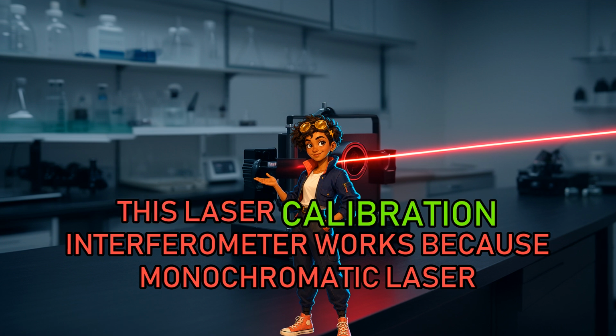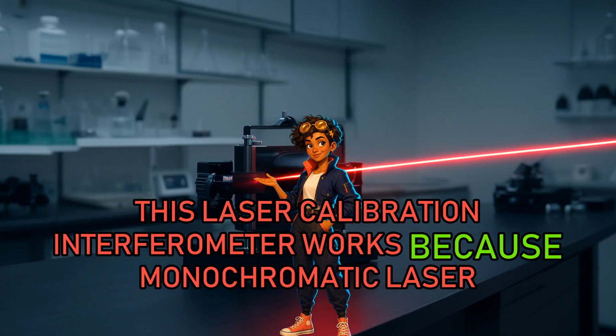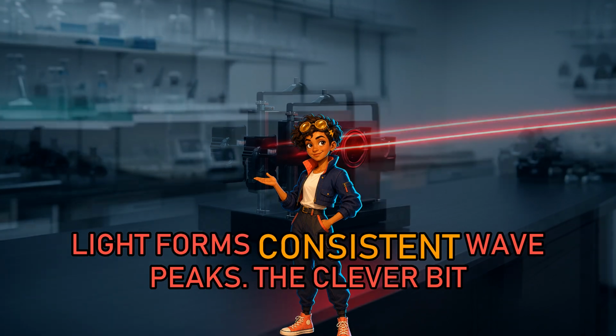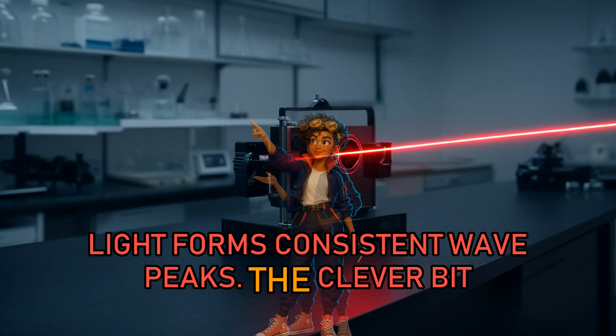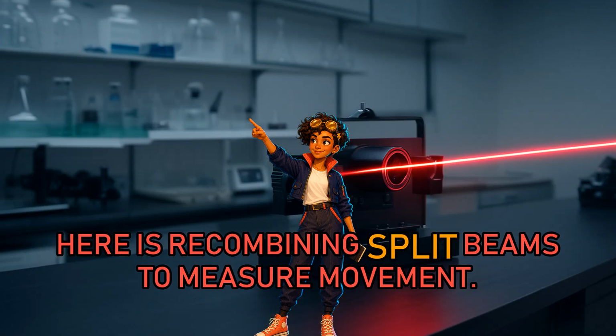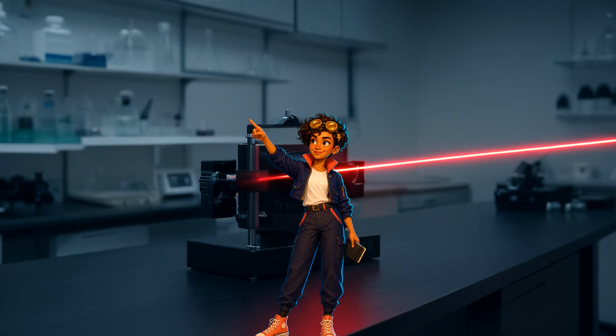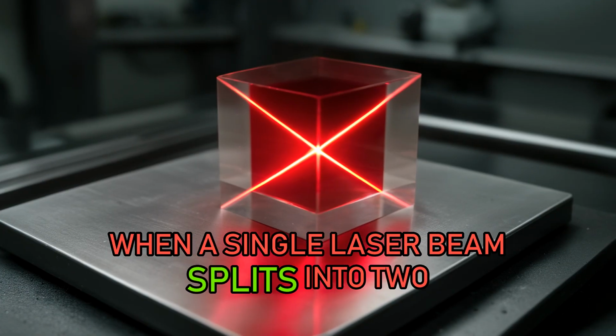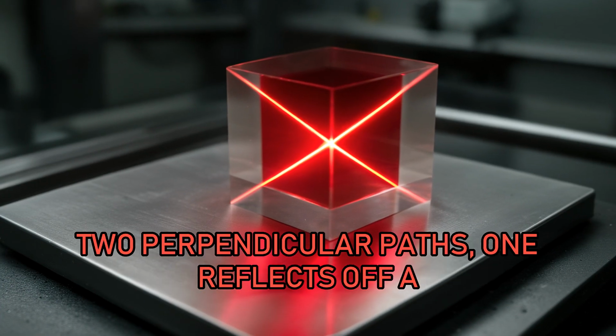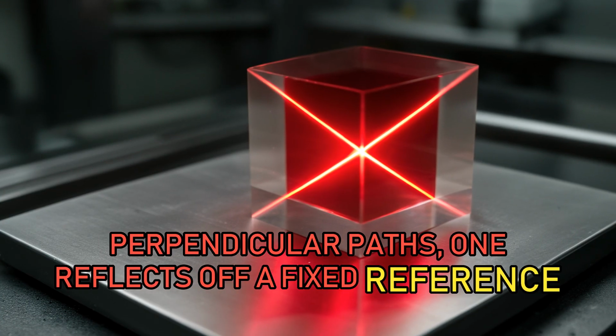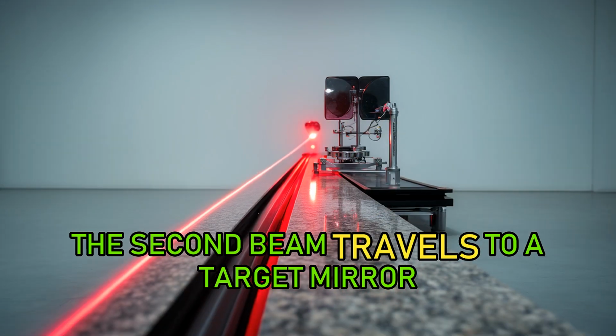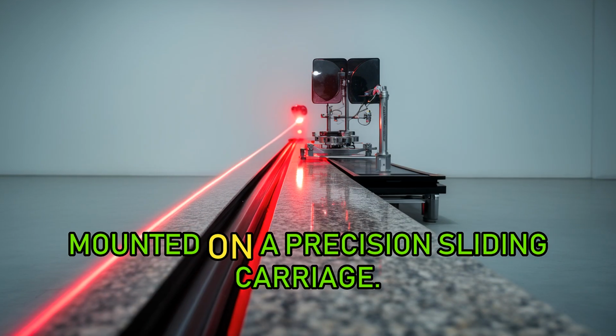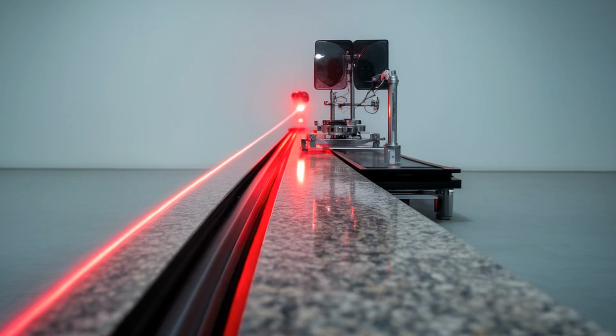This laser calibration interferometer works because monochromatic laser light forms consistent wave peaks. The clever bit here is recombining split beams to measure movement. When a single laser beam splits into two perpendicular paths, one reflects off a fixed reference mirror. The second beam travels to a target mirror mounted on a precision sliding carriage.